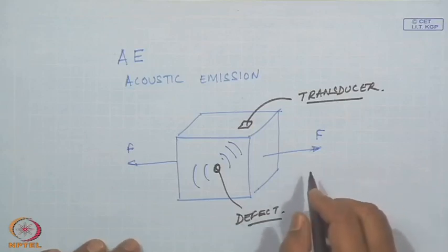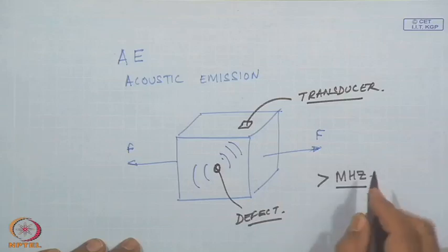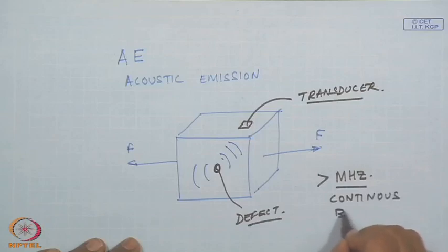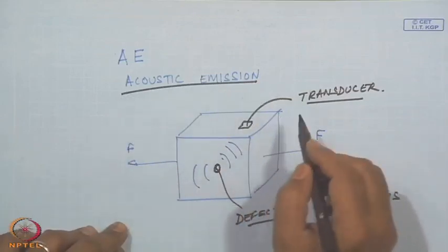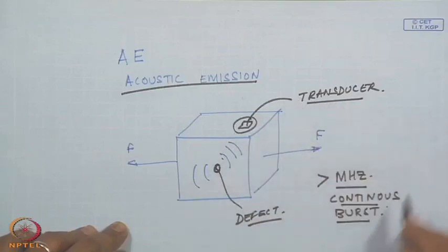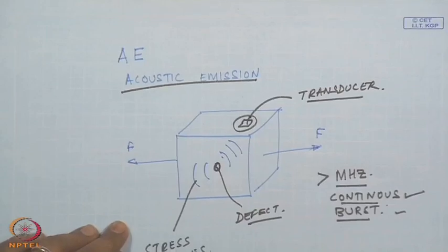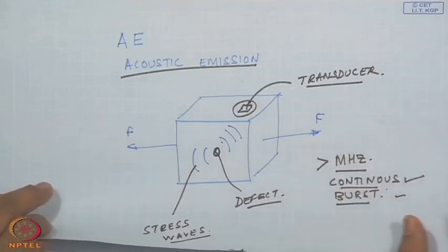There are certain characteristics of this acoustic emission signal. First of all, it is in the megahertz range. It is either transient — in the form of a continuous waveform — or in bursts of certain energy. The acoustic emission strategy is to detect these stress waves, measure them, and analyze them.